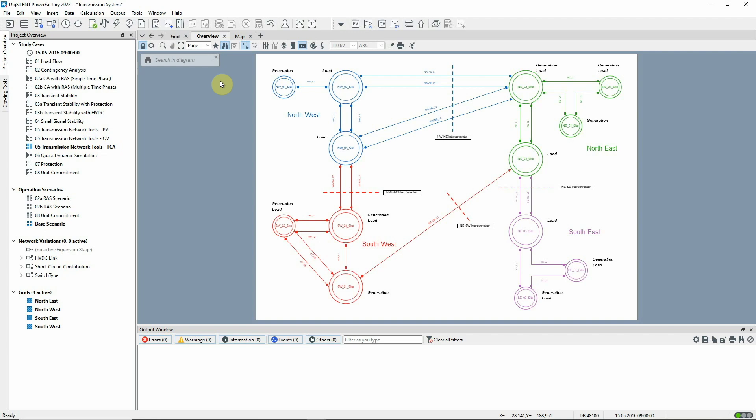Transfer Capacity Analysis is used to determine the maximum feasible power flow between two parts of a network by scaling demand or generation in opposite directions in the two parts. Load flow calculations are executed at each step until the critical point is reached.